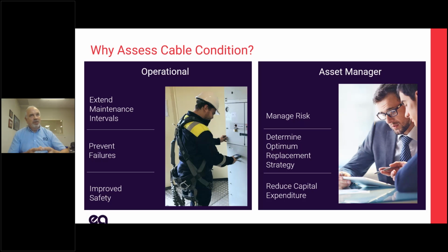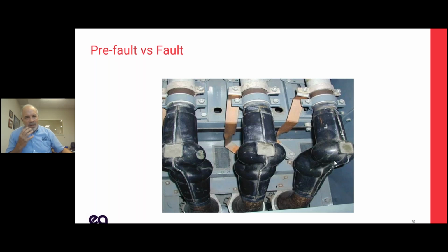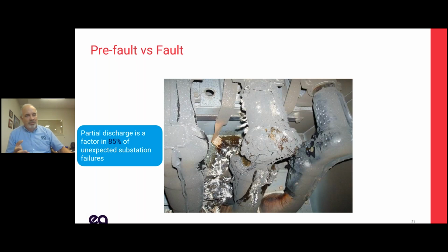And maybe you have a redundancy strategy. Or maybe you go to the asset manager and say, we need to schedule some replacements here. There are lots of reasons to know why your cables are showing issues. And obviously, replacing a cable before it fails is going to be a lot easier. If you look at this picture, would you rather replace one of these terminations, or this one, which was a few weeks later? So you want to get to these things and fix them when you can. And partial discharge, which we started out with, is a factor in some 85% of unexpected substation failures. We've seen that over the years. Partial discharge is starting to break down insulation, and breakdown of insulation is what causes substation failure. So the 85% just kind of makes sense.